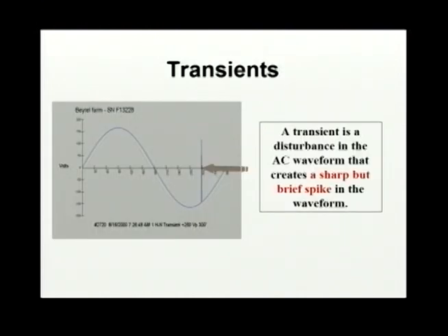A transient is a rapid voltage or current spike that occurs on the waveform. The spikes are usually of short duration, but may be very high voltage, as with a lightning strike. Opening and closing of switches and discharge of capacitors on power lines also produce transients.